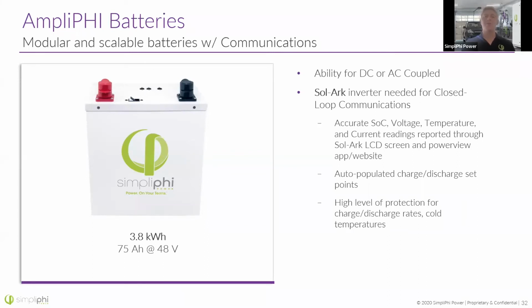So those of you who are familiar with sizing our systems, we know that for the PHI batteries, you need, let's say, five of the PHI 3.8s to fully power an 8 kilowatt Radiant or a Sol-Ark 12K. With the AmpliPHI battery, you can start with as little as one battery for a Sol-Ark 12K inverter. And the reason for this is it can still communicate to the inverter and say, hey, there's only one battery in the bank right now.